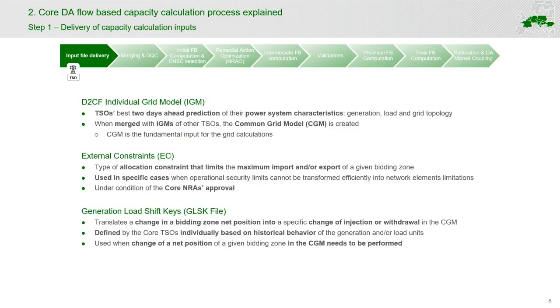Firstly, I would like to talk about the D2CF individual grid model. D2CF stands for the fact that the model is a two-day-ahead prediction of the status of the power grid. It includes the best prediction the TSO has about the generation, the load, the grid topology, and the planned outages such as maintenance. It is actually 24 files because TSO makes a separate prediction for every hour of the day. This file, when provided to the capacity calculation process, is merged by the merging entity to create the common grid model, which is the most crucial and fundamental input for the whole capacity calculation.